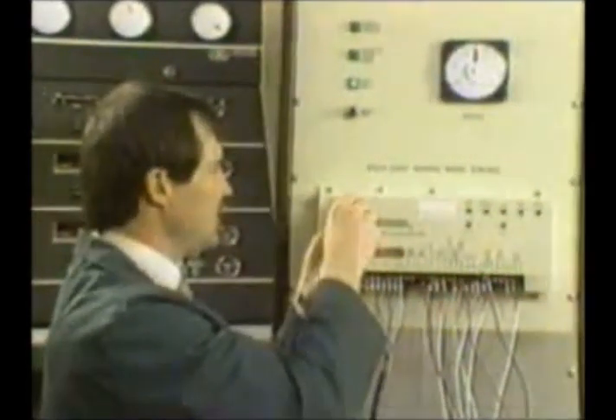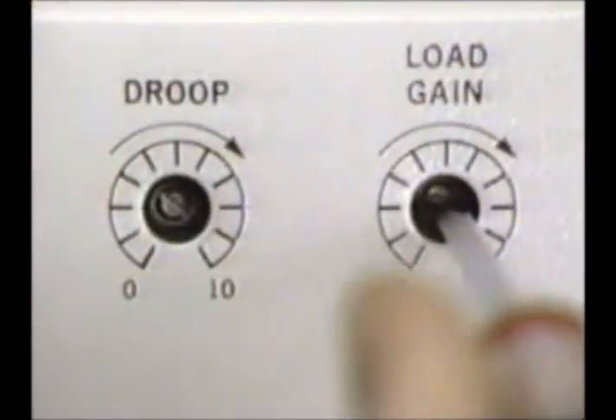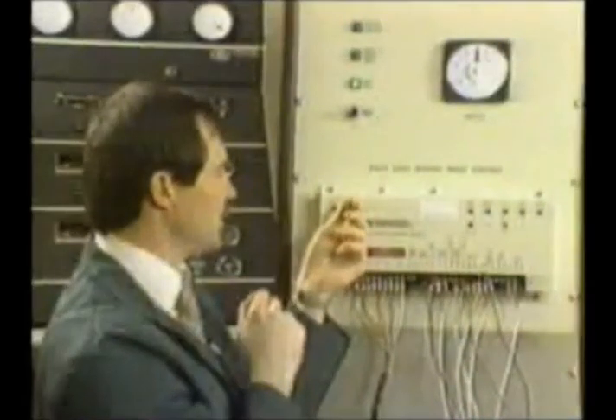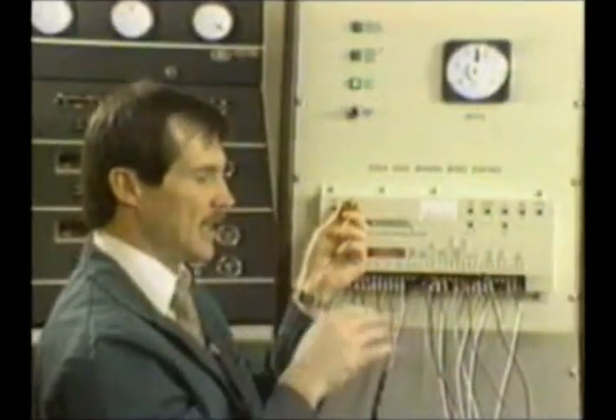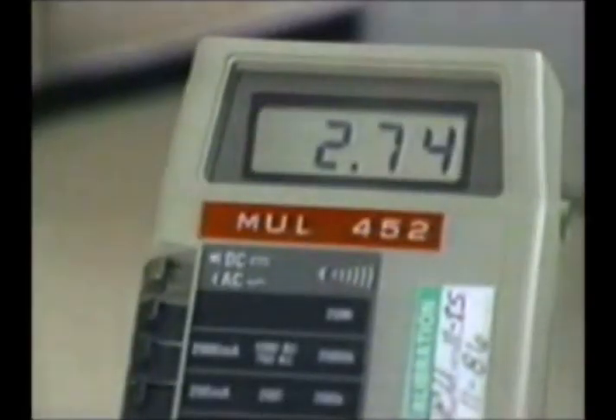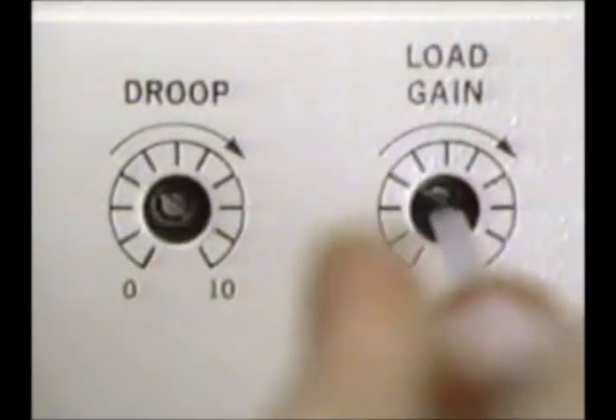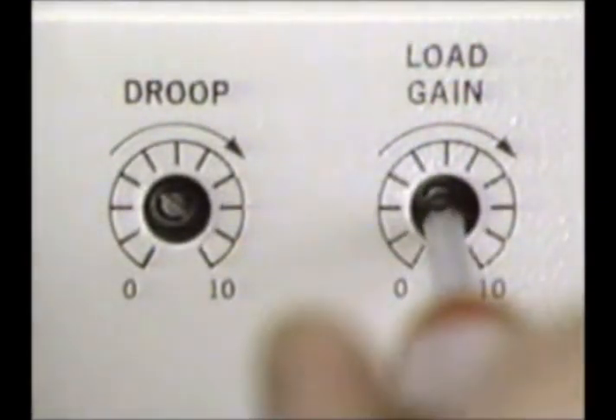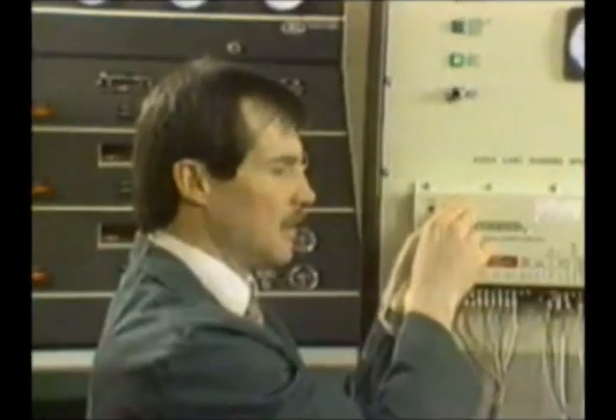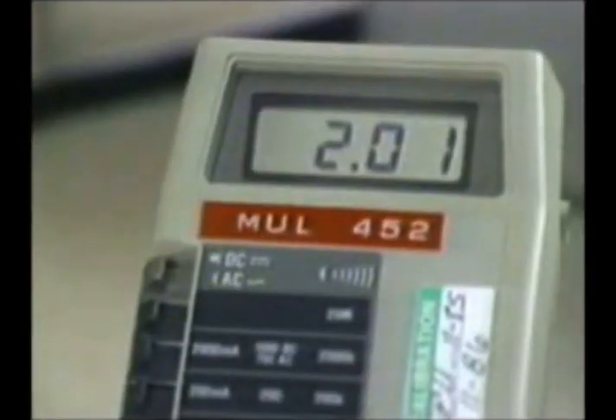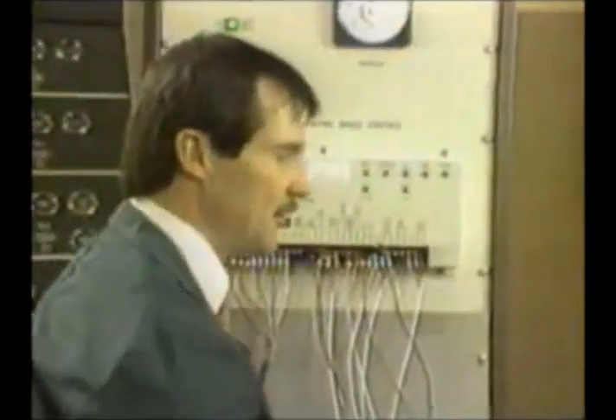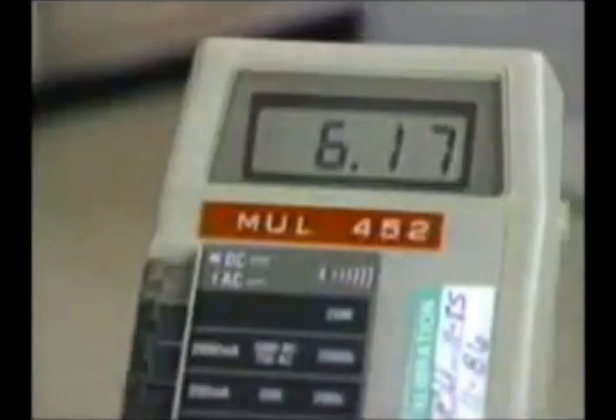So let me go ahead and turn this voltage up. I turn my load gain voltage fully clockwise. I can get just under 3 volts out. So now I'm going to back this off and set it for 2 volts. So now I'm set for right around 2 volts on my load gain. Now I'm going to put on the rest of the load, and when I get up to 100% load, my load gain voltage should read right around 6 volts. Should be very close to 6 volts. Put on the last load, we're up to 100% load.